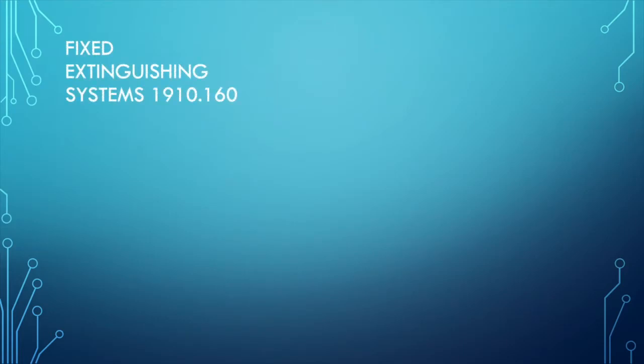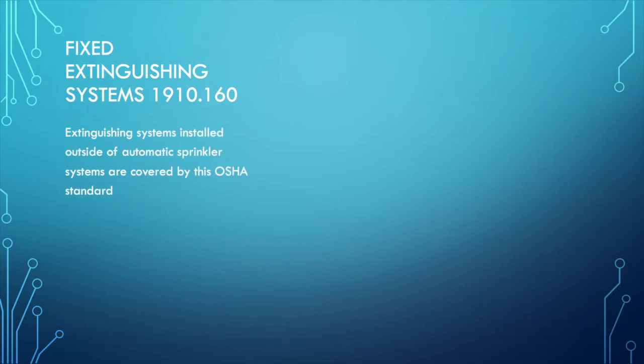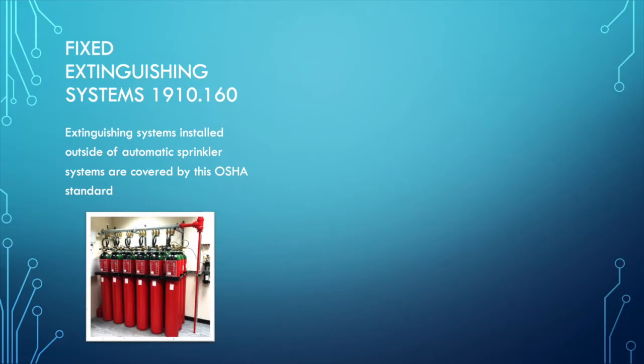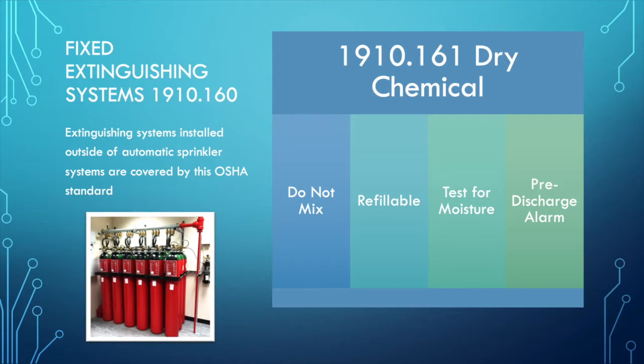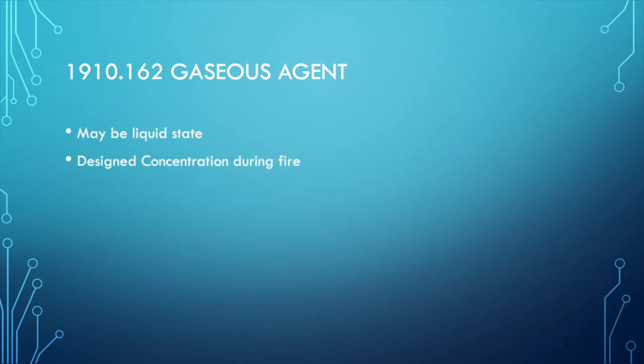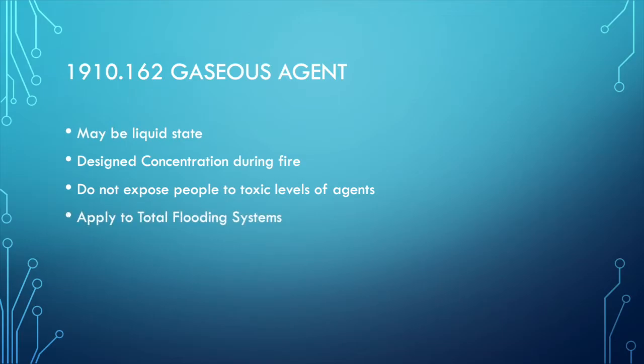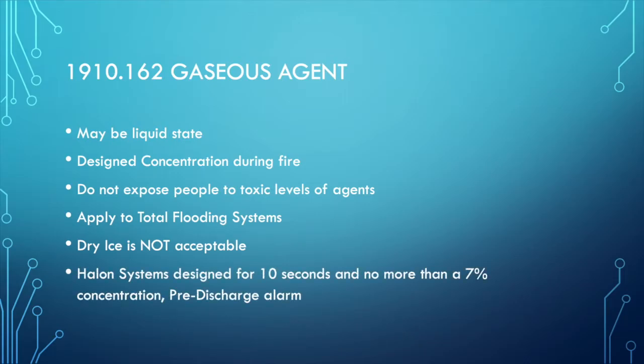Fixed extinguishing systems, 1910.160. Extinguishing systems installed outside of automatic sprinkler systems are covered by this OSHA standard. Gaseous agents may be in a liquid state. Design concentration during fire. Do not expose people to toxic levels of agents. Applies to total flooding systems. Dry ice is not an acceptable gaseous agent. Halon systems designed for 10 seconds and no more than 7% concentration need a pre-discharge alarm.